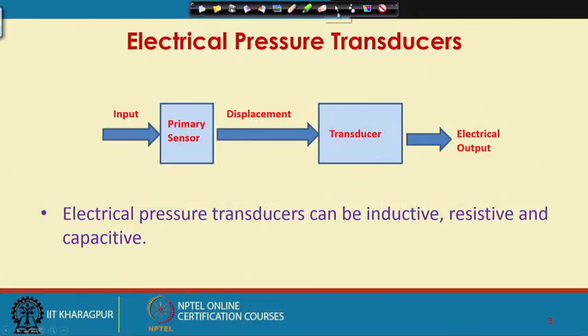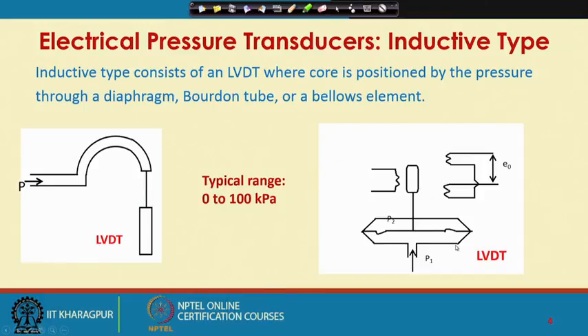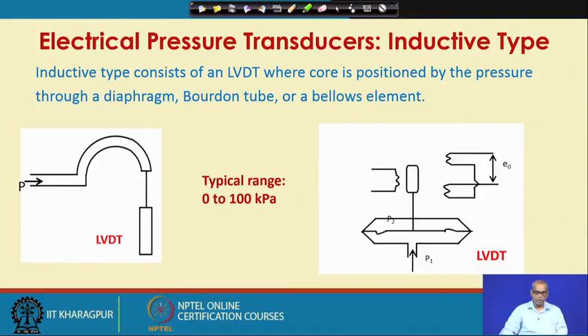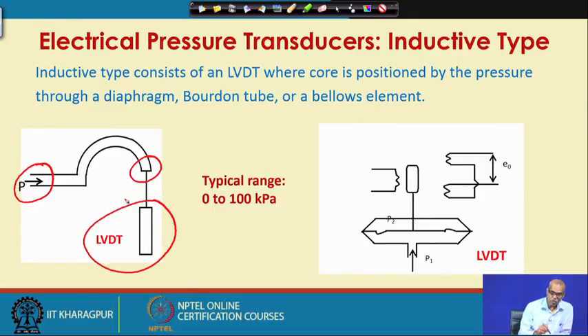Now, let us talk about first the inductive type electrical pressure transducer. An inductive type electrical pressure transducer consists of an LVDT or linear variable differential transformer, where the core is positioned by the pressure being applied through a diaphragm, Bourdon tube or bellows element. So, you apply pressure here in this Bourdon tube, we have learnt in previous classes that there will be deflection of this tip of the Bourdon tube. Now, I make use of LVDT to convert this displacement to an electrical signal.